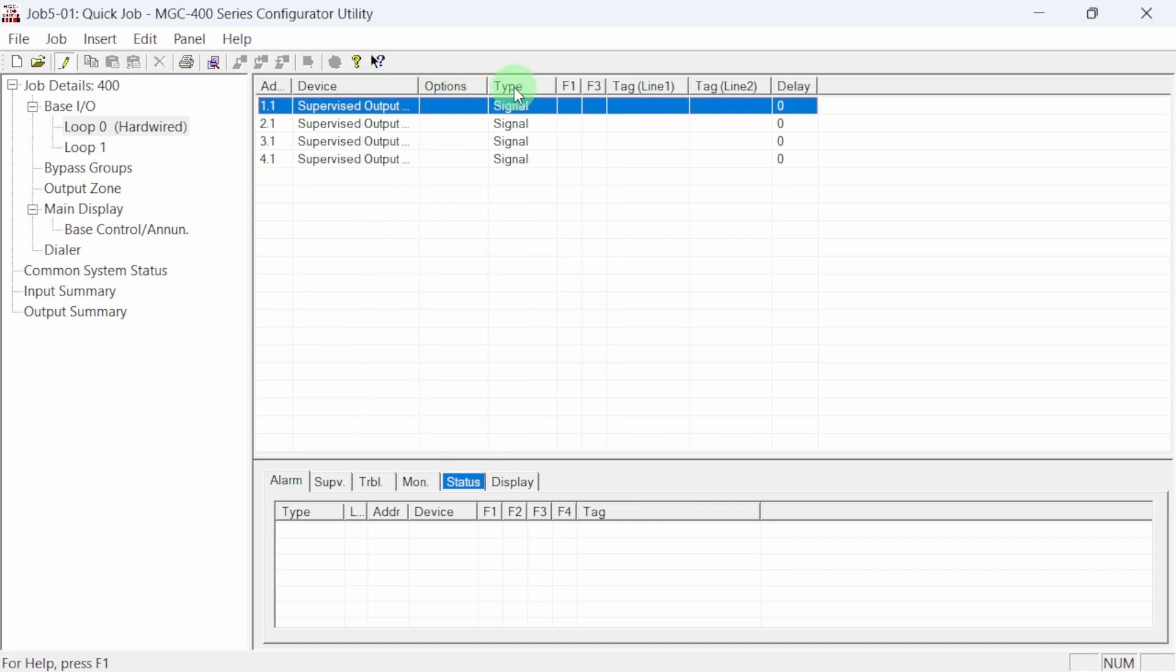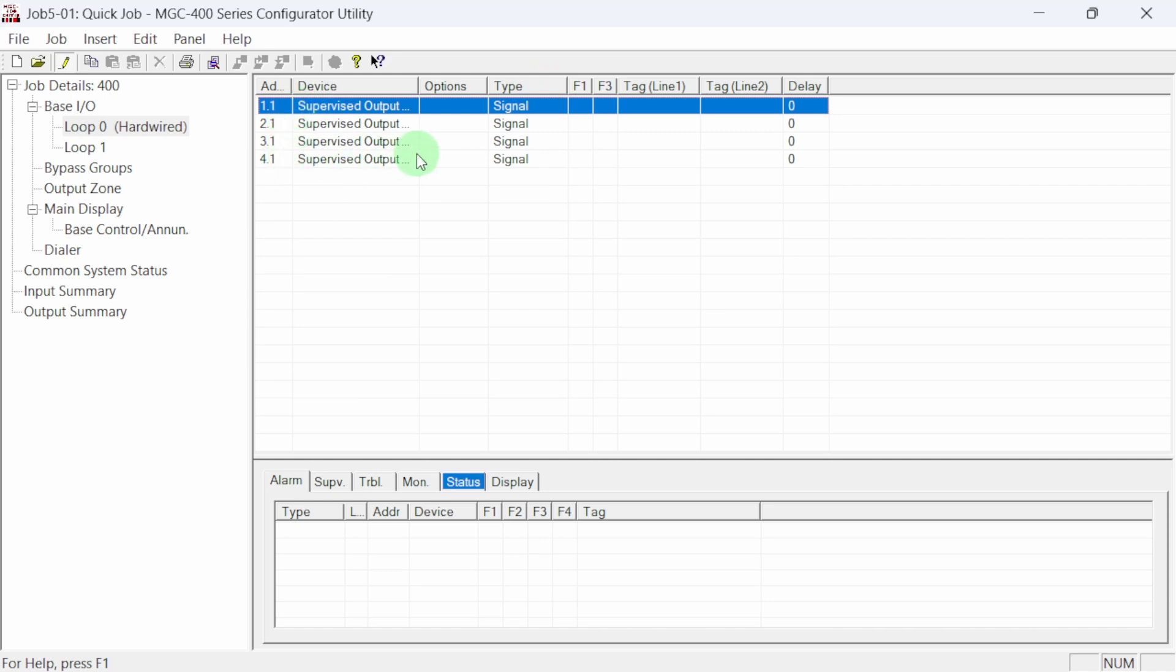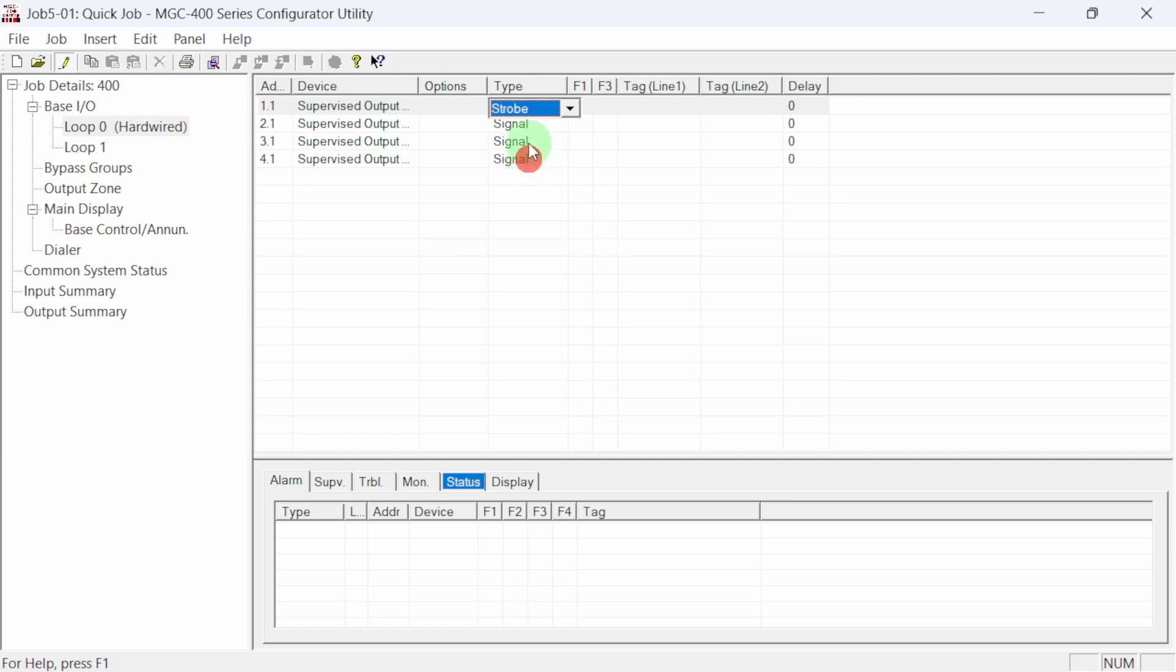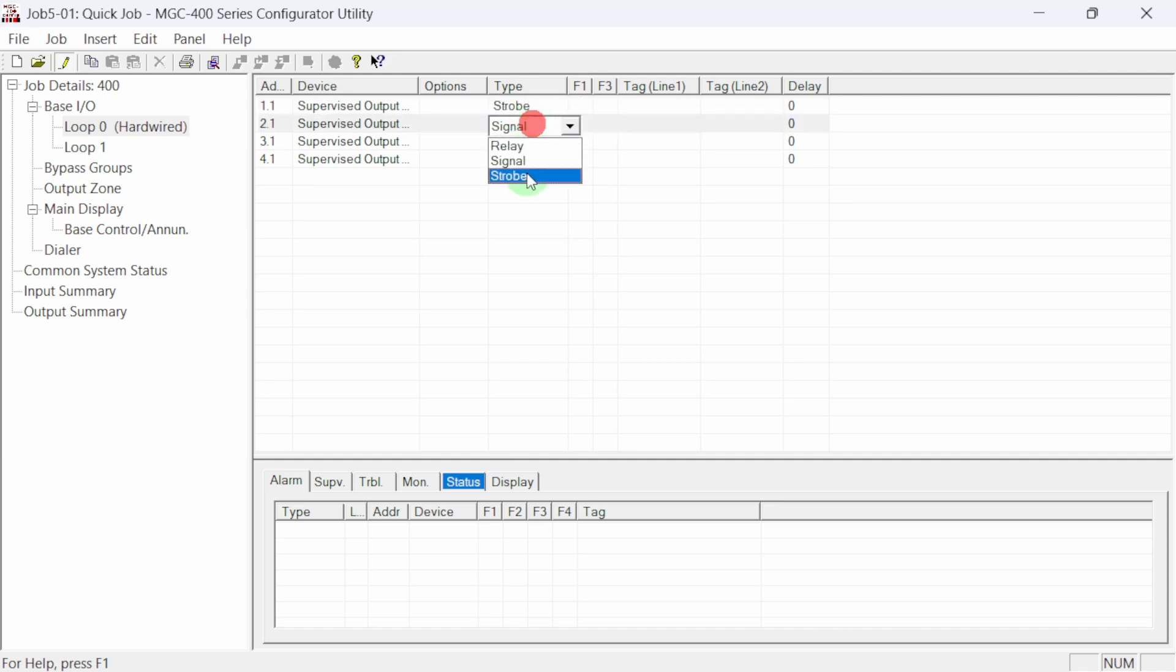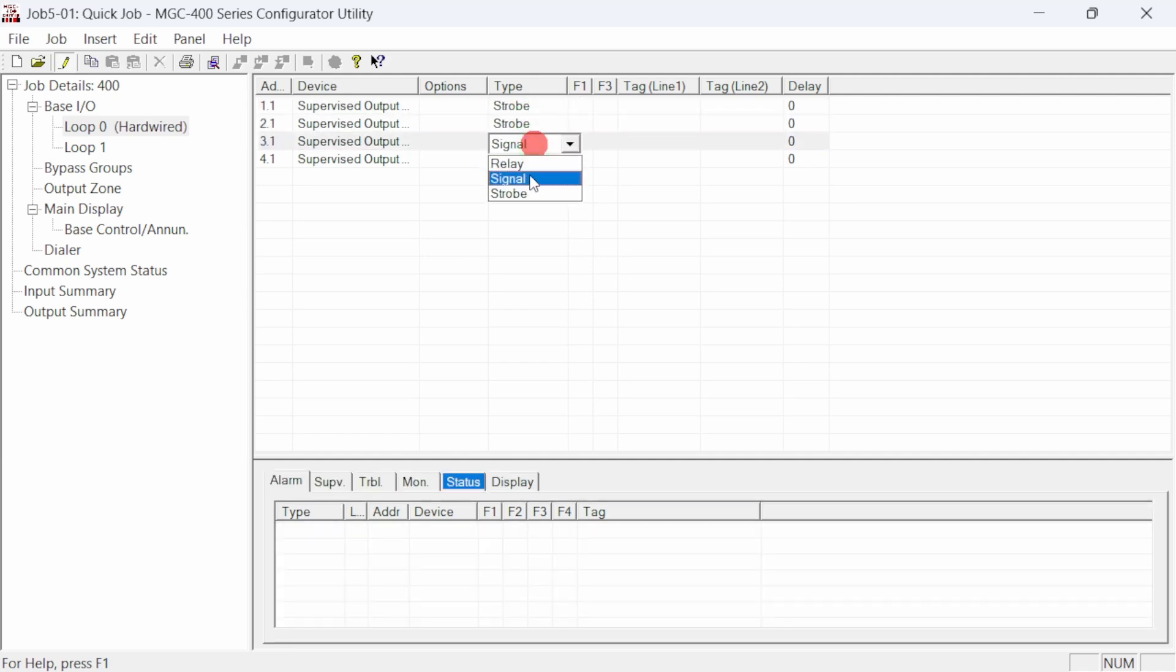Across the top are columns that can be expanded to expose more of a cell's area. The first column shows the circuit number of the four NAC circuits. The circuit type should be changed to strobe to allow the manufacturer's sync rate to be produced. Clicking in the cell allows us to modify the selection.